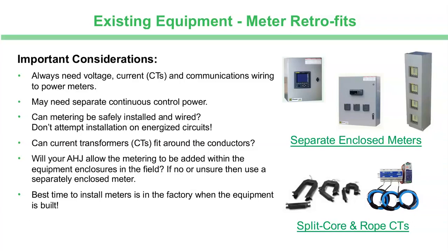One other quick note, I did mention the CTs. I show a couple different types here on the bottom right-hand side. You see that there is a split core where one of the ends of the CT actually snaps on and off, so you can slide it on conductors. And then the other side on the far right side is a rope CT, which is actually what's known as a Rogowski coil. But it's a flexible rope that you can loop through the conductors to make sure you've got everything connected. It's very flexible. It is a little more expensive, but it can solve some big problems. So there's a lot of technology there.